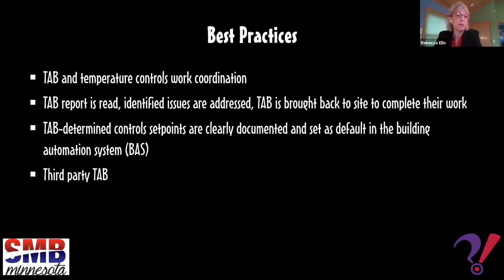Then the commissioning process should confirm that the set points in the control system were determined by the TAB process and not just estimated by the controls contractor. If not, there will be an action item in the commissioning action list for the TAB contractor and controls contractor to coordinate with each other like they should have done in the first place.